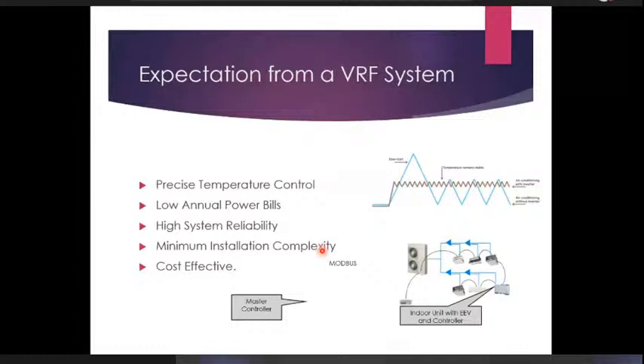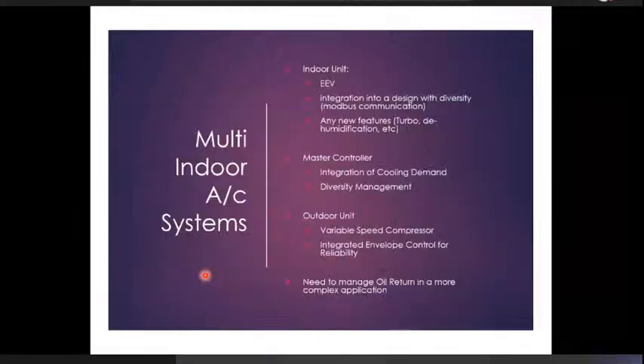Now we look at what are the new things in a multi-indoor AC system. So we need to have an electronic expansion valve. We need to have an element of diversity with Modbus communication. So that means how many units can we connect with one outdoor unit. Typically, diversity brings into fact that we can increase the capacity of indoor units a little more than the capacity of the outdoor unit, because not all of them will operate at their full load all the time.